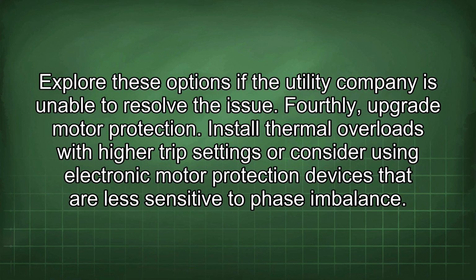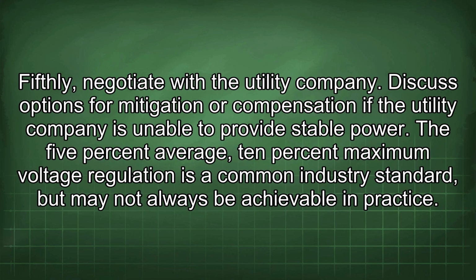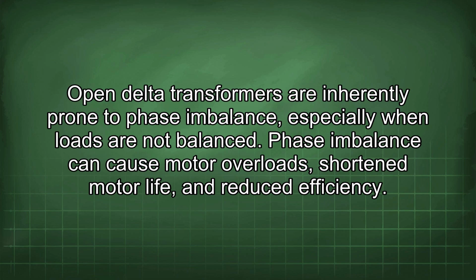Fourthly, upgrade motor protection. Install thermal overloads with higher trip settings or consider using electronic motor protection devices that are less sensitive to phase imbalance. Fifthly, negotiate with the utility company. Discuss options for mitigation or compensation if the utility company is unable to provide stable power. The 5% average, 10% maximum voltage regulation is a common industry standard, but may not always be achievable in practice. Open delta transformers are inherently prone to phase imbalance, especially when loads are not balanced. Phase imbalance can cause motor overloads, shorten motor life, and reduce efficiency.